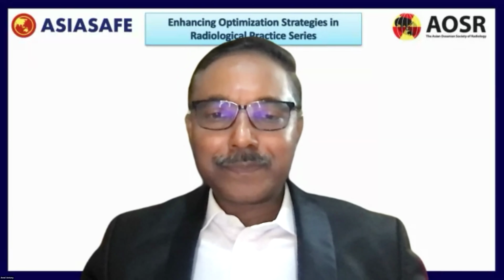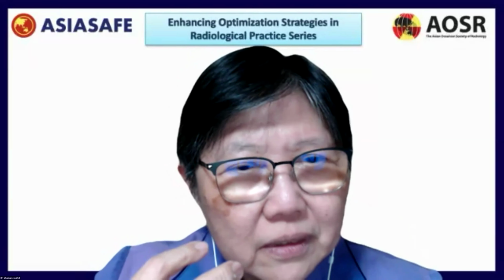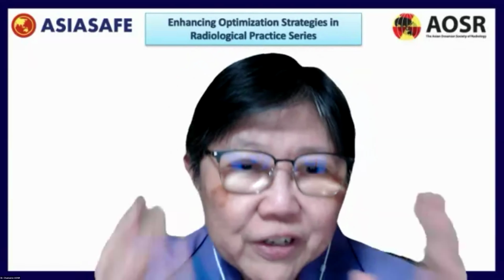So with CR versus DR in mammography, was that the question? The answer is, the QC is going to be the same in the sense that you use the same phantom, but the outcome will be different.